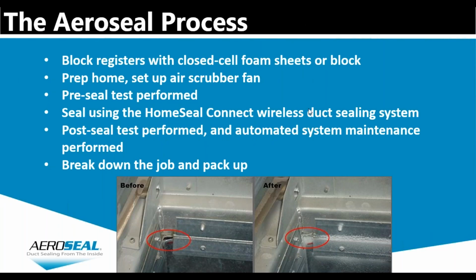A little bit on the Aeroseal process itself. The contractors would go into the home, block the registers with closed cell foam sheets, and isolate the equipment. They prep the home and set up an air scrubber fan, and this is in an existing home situation. In new construction, it's not necessary to do that, but the pre-seal test is performed next. This is basically a duct blaster test that shows what the duct efficiency is at the starting point.